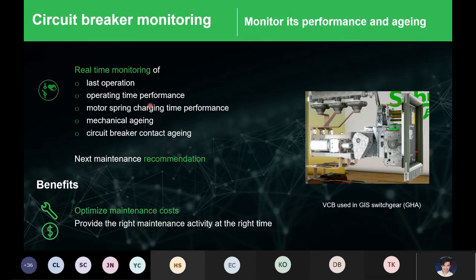Once the whole installation has been done with the sensors, we can basically bring the information into real-time monitoring. You can see the last operation, the operating time, and even the lifespan and the aging of the circuit breaker as well. So in a way, the panel starts to become digitized for your switch gears, and then you start to communicate with the end users. This also brings certain benefits in terms of operating expense being reduced, and it reduces the maintenance cost as well.